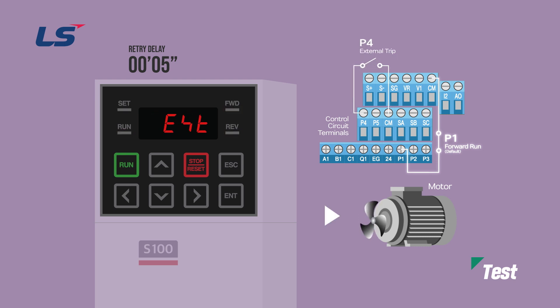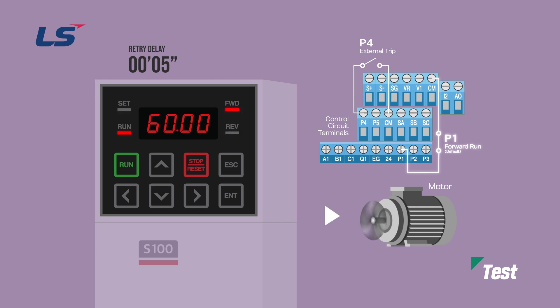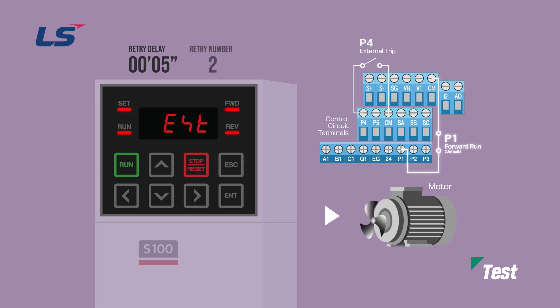Repeat the same method several times. Since we set the number of restarts to 2 earlier, we can see that after the third external trip occurs, turning P4 off will not restart the motor.